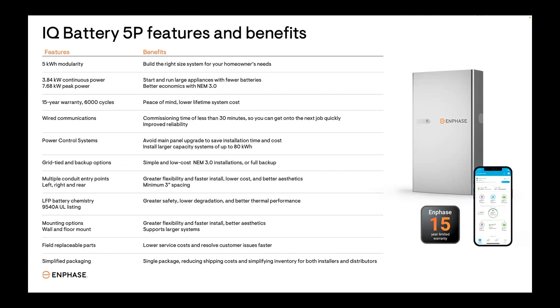Another big benefit to the 5P is that it uses wired communications hardware instead of wireless. The previous generation used wireless, as you probably know, using Zigbee technology. That had some limitations in terms of how far away components could be placed from one another. You had to keep things relatively close together for good quality wireless communication. It also increased the commissioning time because it was just kind of a long process for the components to talk to each other during commissioning over Zigbee.